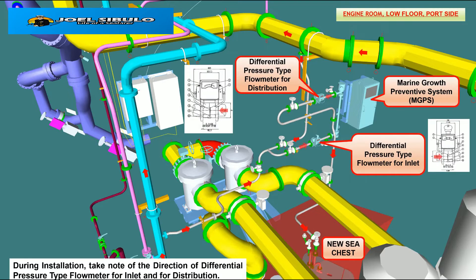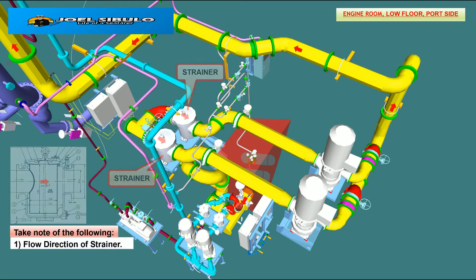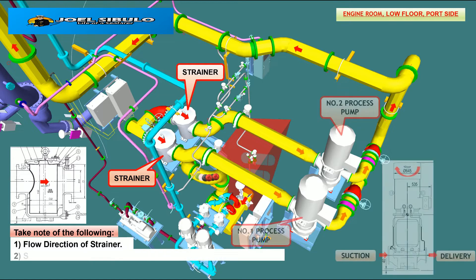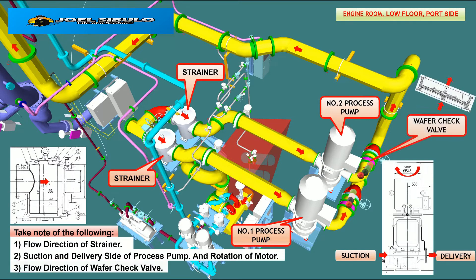During installation, take note of the direction of the differential pressure type flowmeter for inlet and for distribution. Take note of the following: the flow direction of the strainer, the suction and delivery side of the process pump and rotation of motor, and the flow direction of the wafer check valve.